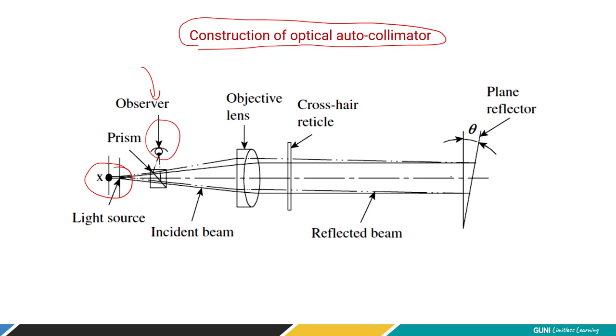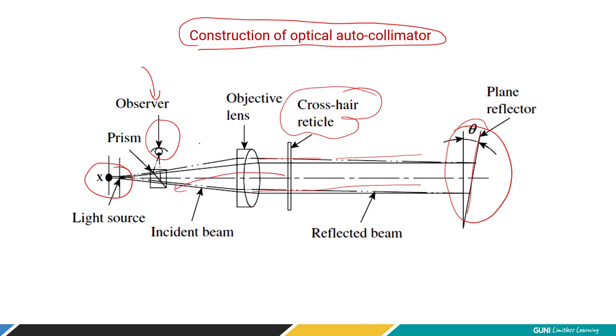In the construction of the optical autocollimator: there is a light source, an eyepiece from which you can observe the reflected image, and a prism used so you can observe images coming from the mirror surface or plane reflector. Light initially passes through the objective lens and travels as parallel beams. These parallel beams are reflected from the inclined surface. There is a crosshair object, and this crosshair image is taken back after reflection and observed. If the surface is perfectly perpendicular at 90 degrees with no angular deviation, the image will be perfectly observed in the eyepiece.